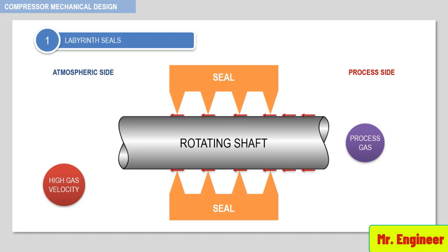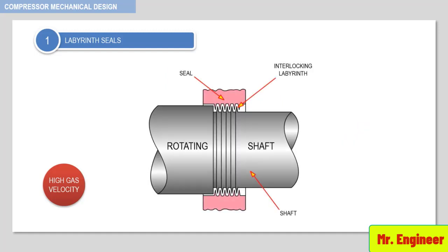In such cases, an interlocking labyrinth seal can be used. As shown in this example, the shaft also has teeth which interlock with the teeth of the seal, thus preventing flow of gas in a straight line.